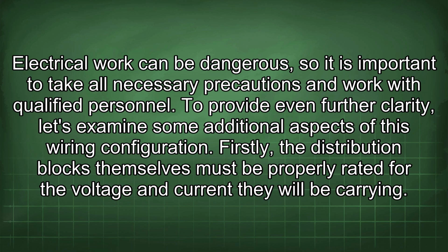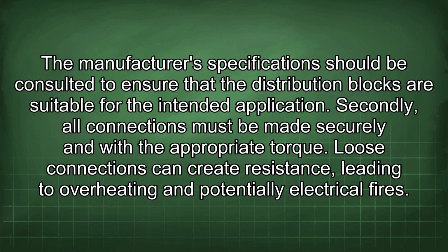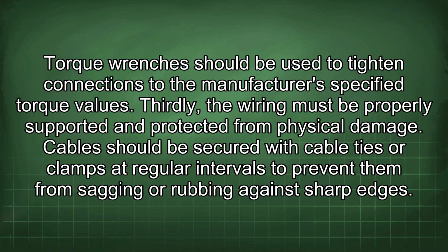To provide even further clarity, let's examine some additional aspects of this wiring configuration. Firstly, the distribution blocks themselves must be properly rated for the voltage and current they will be carrying. The manufacturer's specifications should be consulted to ensure that the distribution blocks are suitable for the intended application. Secondly, all connections must be made securely and with the appropriate torque. Loose connections can create resistance, leading to overheating and potentially electrical fires. Torque wrenches should be used to tighten connections to the manufacturer's specified torque values.